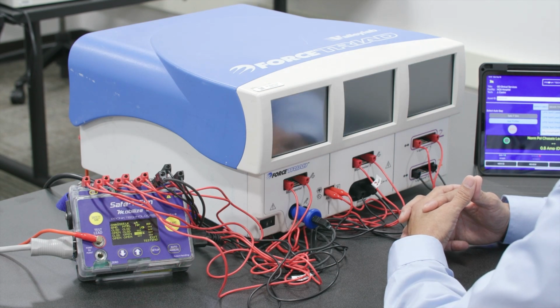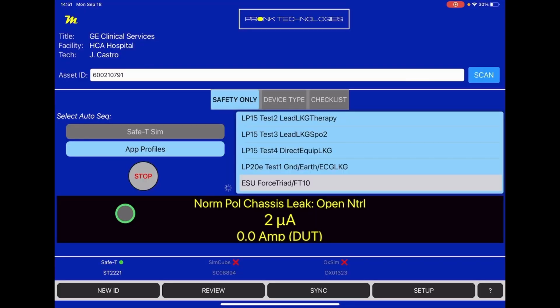Once it's done, it's going to go on to the next test, which is performing a chassis leakage with the neutral open. So once you do the neutral open test, the analyzer will power off. That's normal because we're doing a fault condition when we're simulating that the neutral line is open and doing a chassis leakage test under those conditions, and that's why you see the unit turning off. But we're getting very low leakage in that situation, but nonetheless, that's a requirement of the manufacturer to perform that test. We have to make sure we perform it as well. So it's going to do all of these tests automatically, so we can capture all those results.